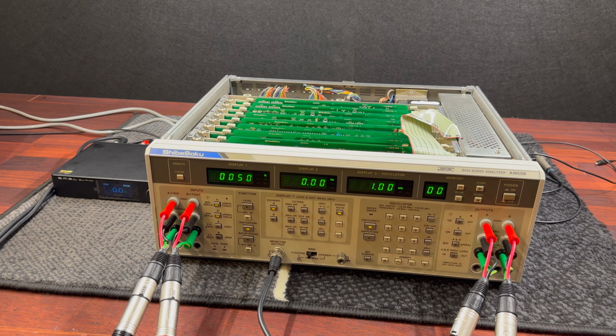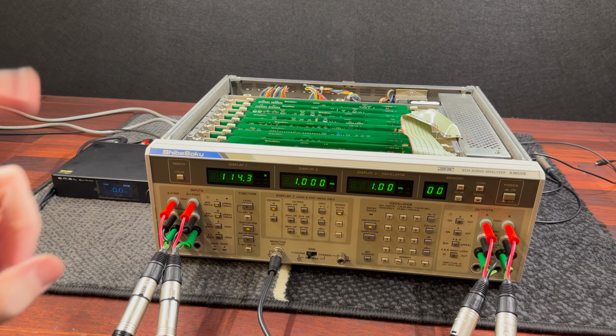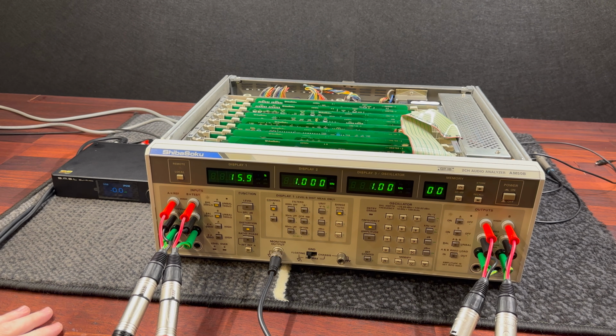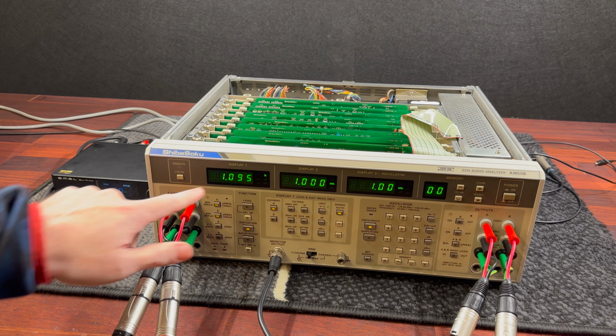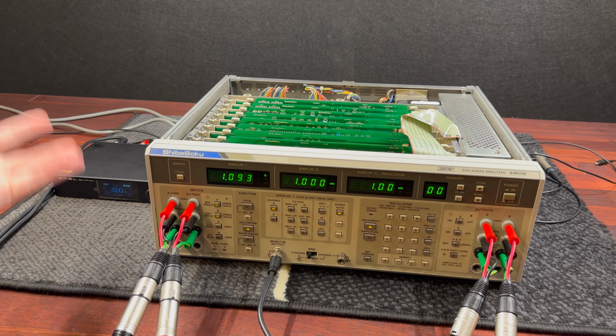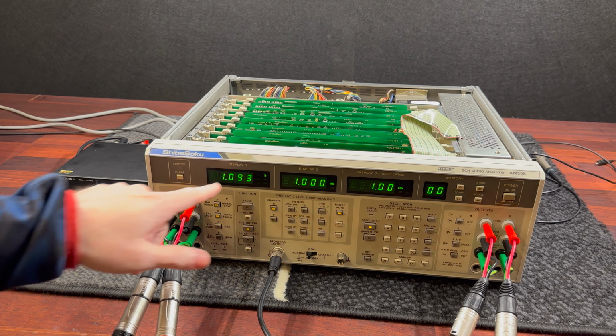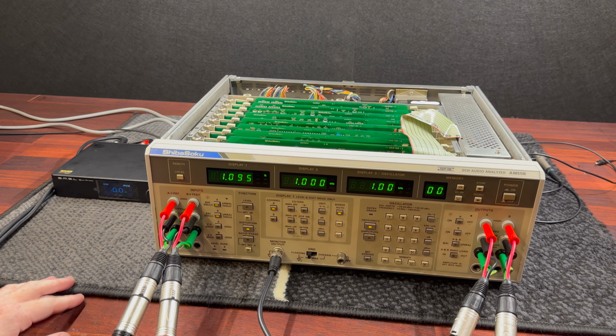In saying all that, let me show you what a 1% total harmonic distortion is supposed to show on this unit with this test file. And this is the reading I get. As you can see, we are reading, yes, 1%-ish. That is 1.09, almost 1.1.